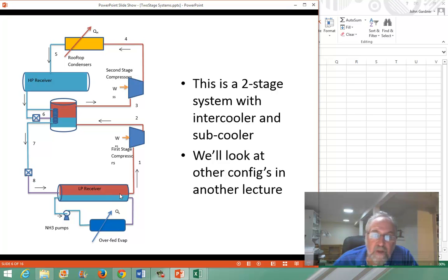Now this tank, the low pressure receiver, is heavily insulated because this is very cold. In these commercial systems, the typical temperature is minus 34 Fahrenheit, which is getting pretty close to where Fahrenheit and centigrade Celsius hit the same place, so it's around minus 38 or 36 Celsius. This receiver is also at saturation, has both phases in it.